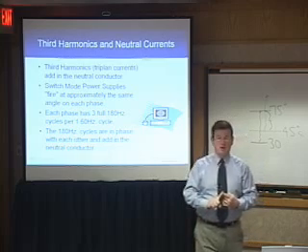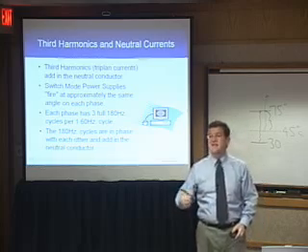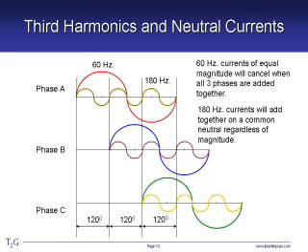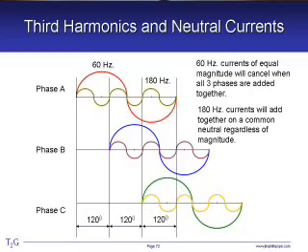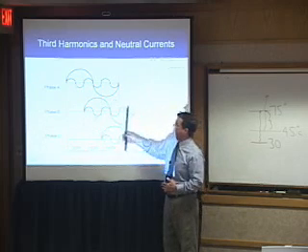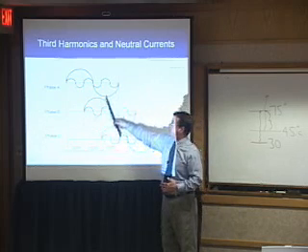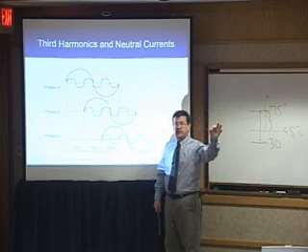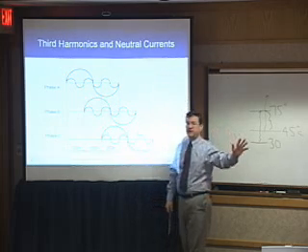The one that's most troubling is the third harmonic — it's 180 Hz current. If we look at a three-phase power system with phase A, phase B, and phase C, the phase currents are all displaced by 120 degrees. If you go along in time and add the magnitudes of A, B, and C, you get zero for the 60 Hz current. That's not the problem.